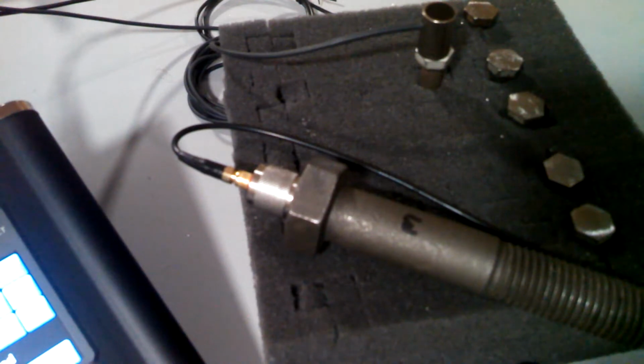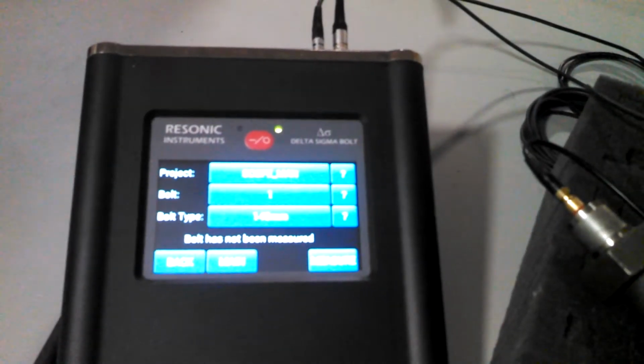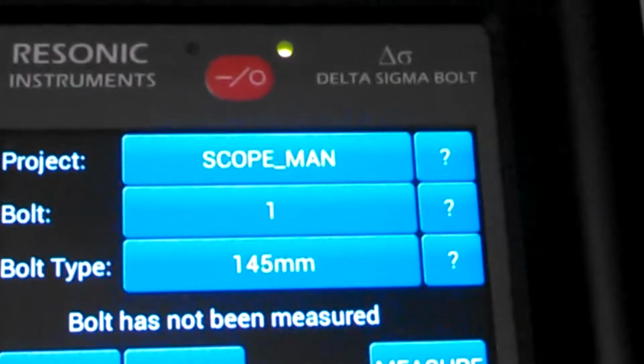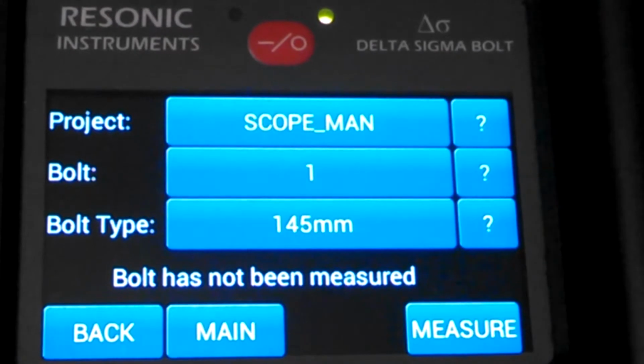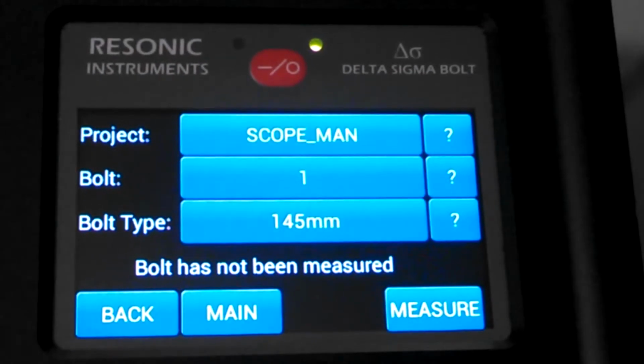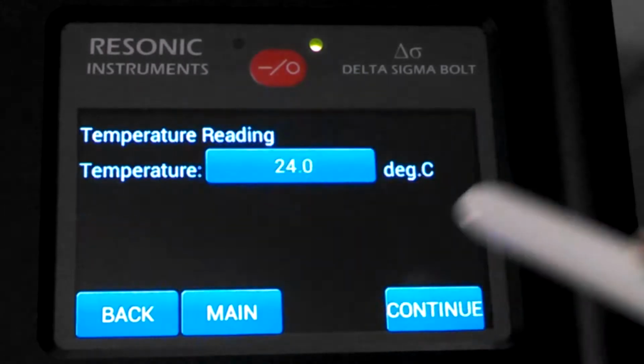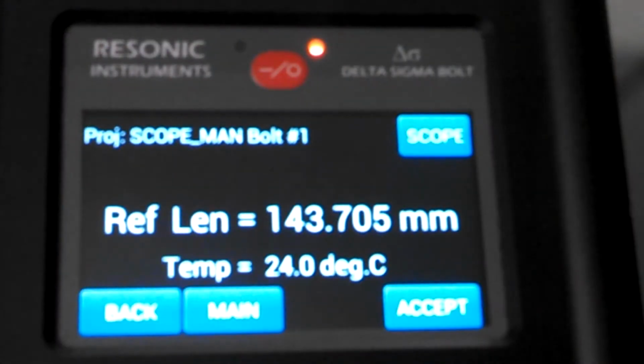So our bolt's all set up. Our temperature transducer is reading the temperature of the ambient room, no problem. So I've already set up the DS1 with a project, and the bolt type is all there. And again, this is just to demonstrate the advanced receiver mode, the manual receiver mode of the DS1. So we'll go measure it. The temperature goes off, it searches, gets the best signal amplitude, sets the threshold. It comes back with a real nice trace.